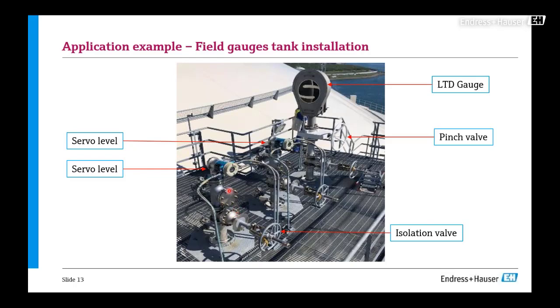Or if you have a smaller displacer, like the 50 millimeter which we often use in LNG storage tanks, you can utilize the calibration window, the isolation valve, the LTD gauge, and the pinch valve here. So these are two references just to show you an example of how the gauge is installed.